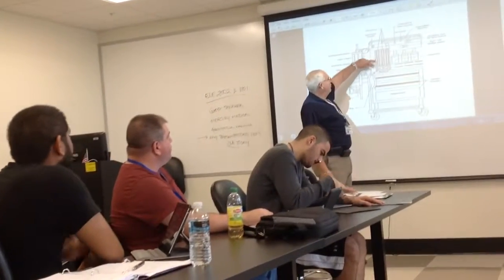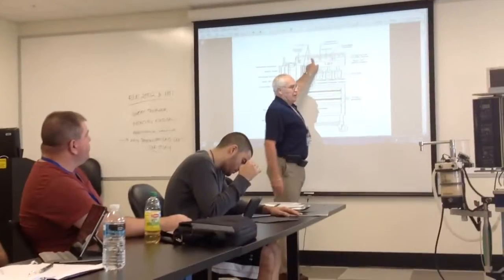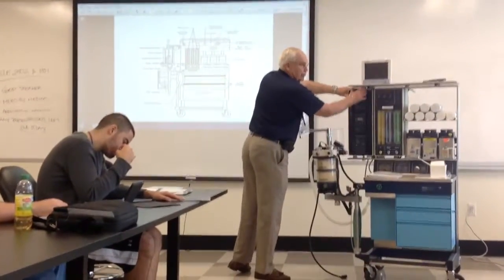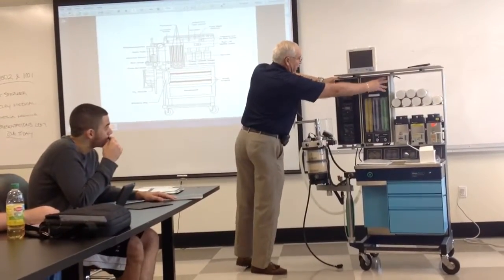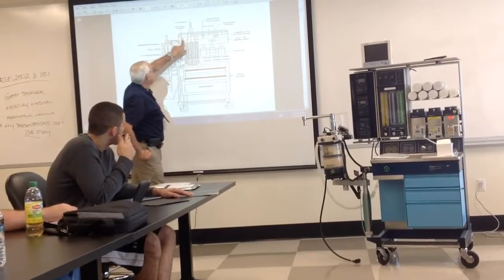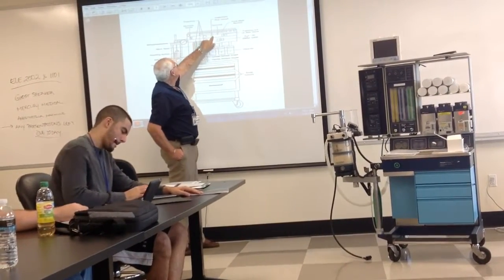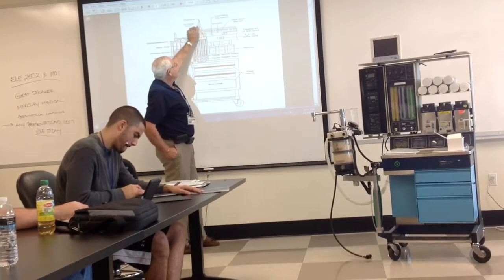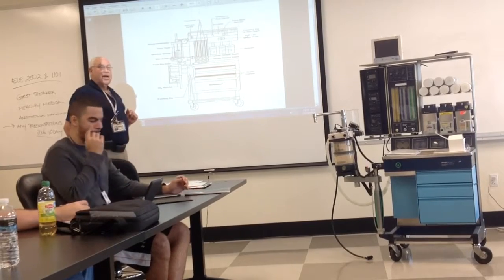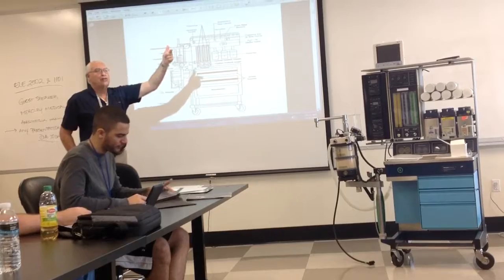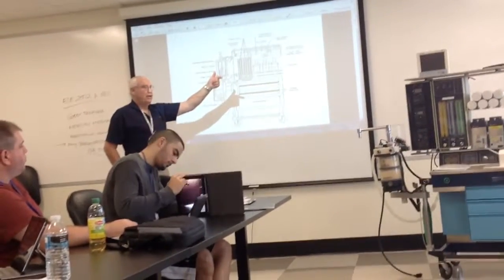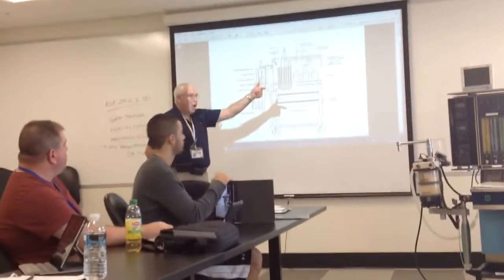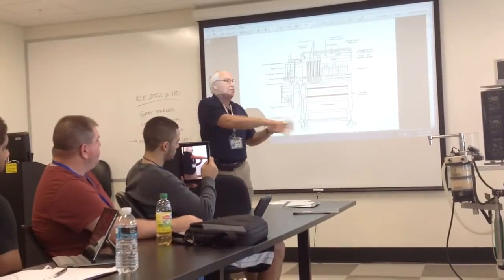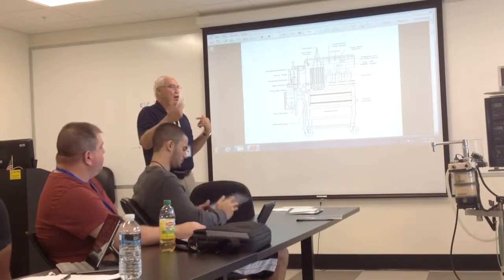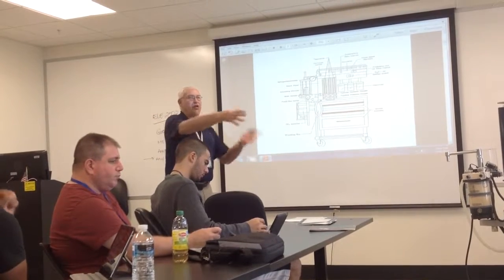On this machine, they have an alarm panel. The monitoring is up here. On this one, the alarm panel and the monitoring is on the side here. The ventilator is up here, and it has some alarms. On this one, the ventilator has an inspiratory flow, it has a ventilator switch, and it has some other adjustments, okay, which are inspiratory to expiratory ratio. When you breathe, people have different ways of breathing. You want to be able to accommodate the machine to mimic what the practitioner sees on the patient before he puts them under.